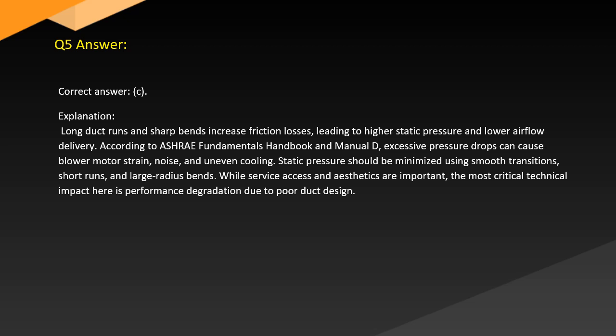Answer. Correct answer: C. Explanation. Long duct runs and sharp bends increase friction losses, leading to higher static pressure and lower airflow delivery. According to ASHRAE Fundamentals Handbook and Manual D, excessive pressure drops can cause blower motor strain, noise, and uneven cooling. Static pressure should be minimized using smooth transitions, short runs, and large radius bends. While service access and aesthetics are important, the most critical impact here is performance degradation due to poor duct design.